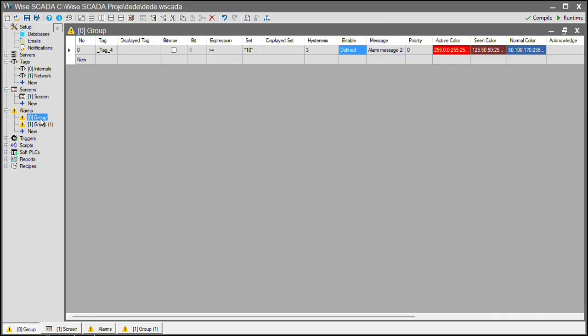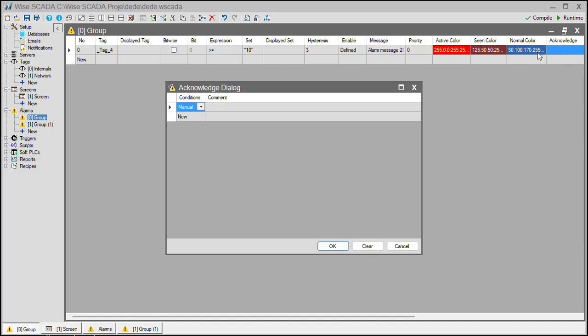One of the most important issues is that in many automation applications, operators do not use the acknowledge option for alarms. Therefore, the list on the screen constantly lengthens and becomes a large list. In this case, manual confirmation by the operator must be made mandatory by using the acknowledge option during alarm definition.